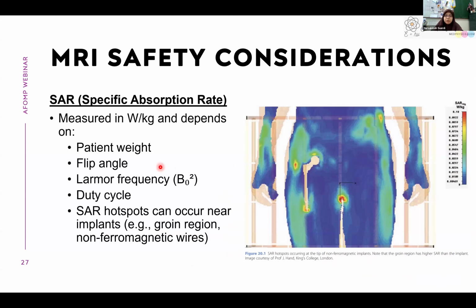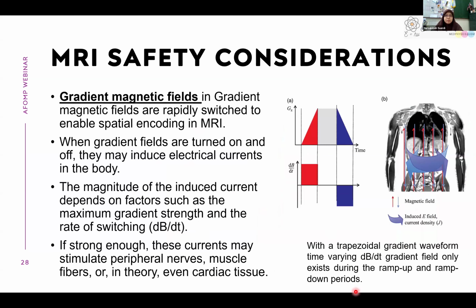And the specific absorption rate is basically measured in watts per kilogram. It depends on the patient weight, the flip angle that you use, the Larmor frequency, the strength of the magnetic field, and the duty cycle. You can also see that the SAR hotspot can occur near the implant. So if there are implant materials, even non-ferromagnetic wires, they may cause more heating hotspots in that area, which you should be aware of.